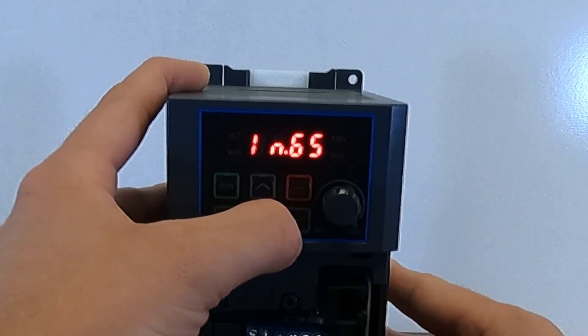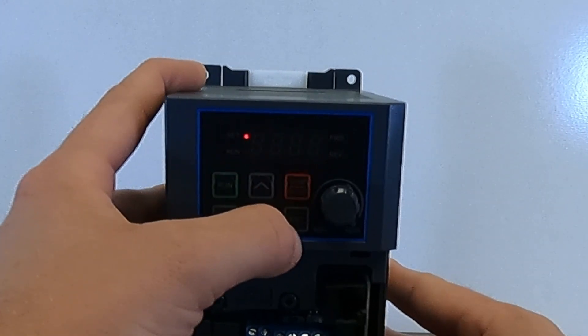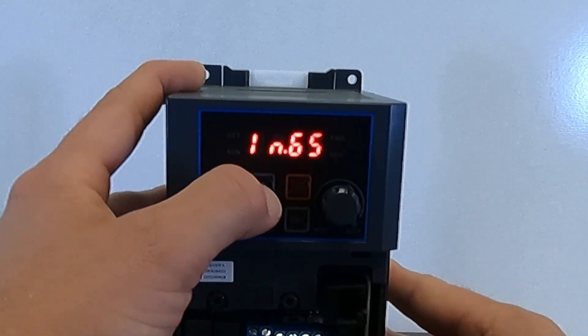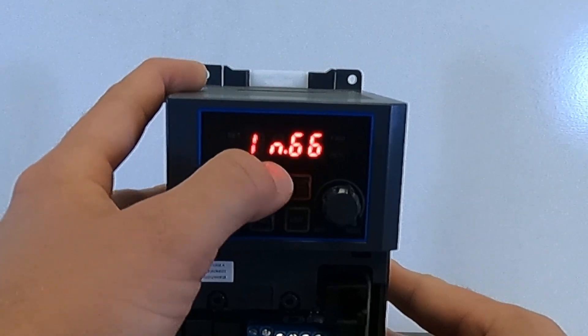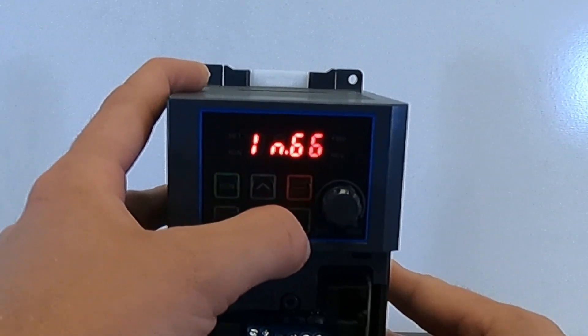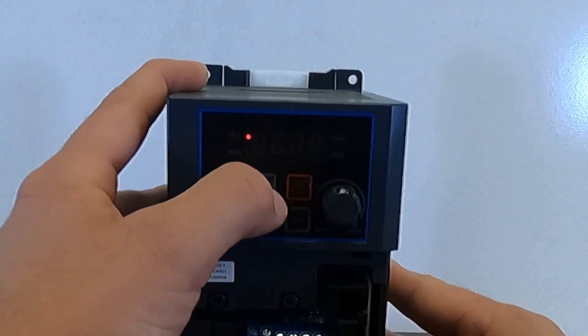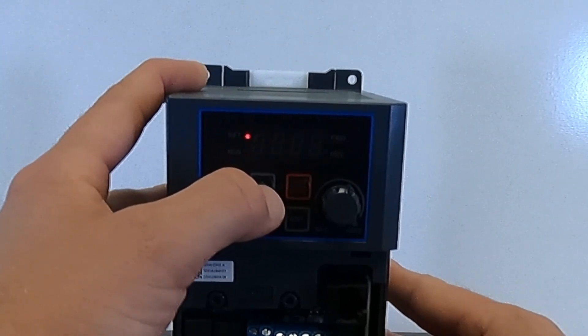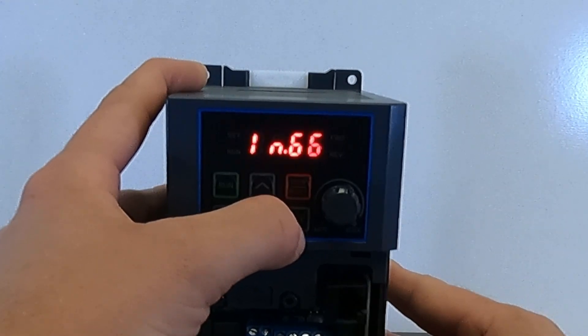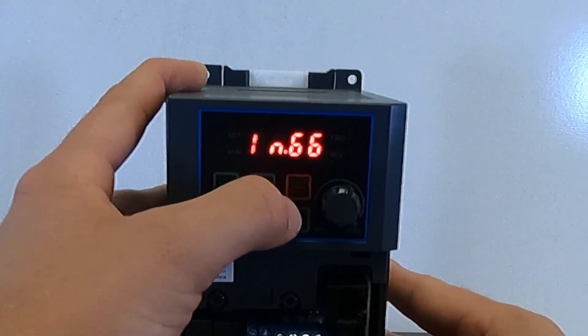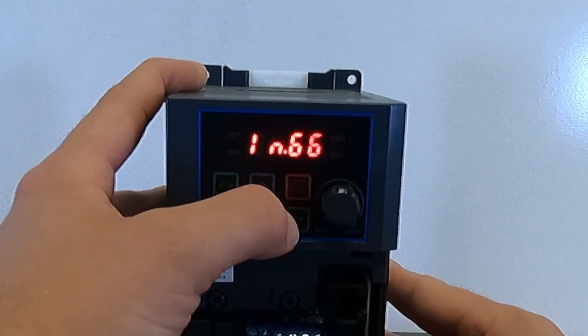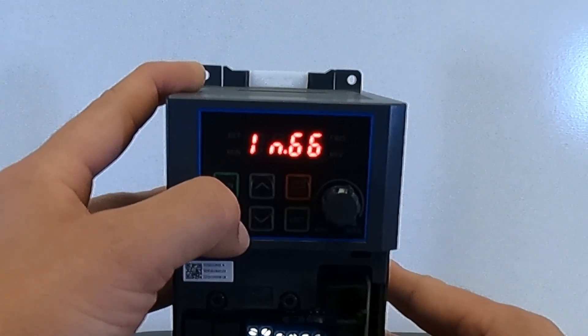We'll hit enter. Default is 1 for forward run command. We will leave that there. We'll go to input parameter 66 for the second input terminal. And we will set that for 14 for three-wire control. And that is where we will land the normally closed stop button on the drive.